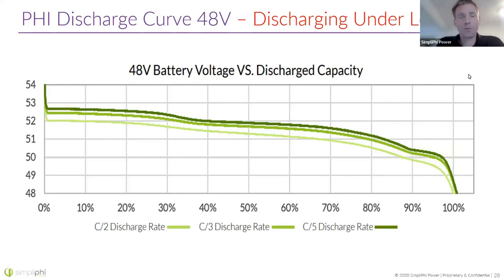When I discharge a battery, you'll notice something that happens, and that's a drop in voltage. A simple circuit would show you that there's some internal resistance inside a battery. So if a battery is sitting at 54 volts and I start to discharge it rapidly, the voltage will drop. And it's not because the state of charge has rapidly or instantaneously dropped. It's because there's a voltage loss inside the battery, and that's proportional to the current you're drawing out of the battery. What I'm showing you here is discharge cycles of a battery that starts at 100% state of charge over here on the left. You can see the voltage that it's starting at. And then as I start to discharge it, gradually that voltage drops, right? And at a C/5 discharge rate, this whole graph would take 5 hours to generate.